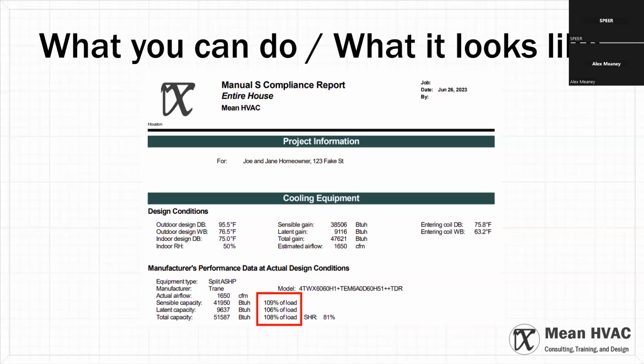Due to some vagaries of how equipment sizing works, it's harder to size equipment in high altitude, dry climates. Adjustments in airflow don't affect system performance as much as in humid climates, because there's almost no latent load to impact. So in dry climates, you'll often get reports showing numbers that exceed the limits, over 115%. Well, there's a reason for that.